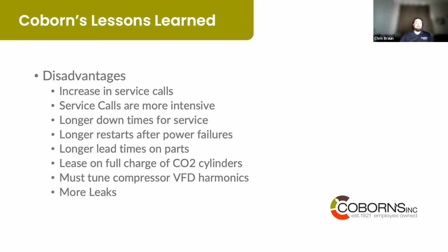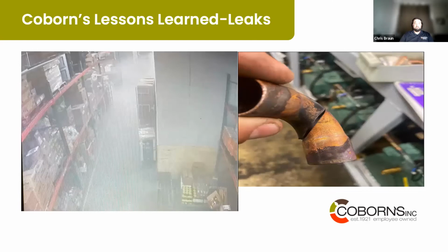But on the plus side, if you go to the next slide, Morgan, this is an incident that we ran into on one of our systems. A 90 failed like that, and it did blow off considerably. That's the vapor from that blowing off in the back room. So that was a pretty large CO2 loss. But it was $2,500 worth of CO2 being lost versus $40,000 to $50,000 worth of HFC being lost in that situation. That is something that we learned. It was due to a mechanical failure in the system that caused vibration, not due to the VFD harmonics I was talking about before, but a valve failure that caused that vibration and caused that crack in that 90.